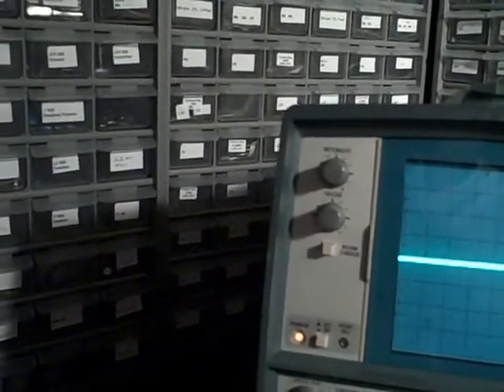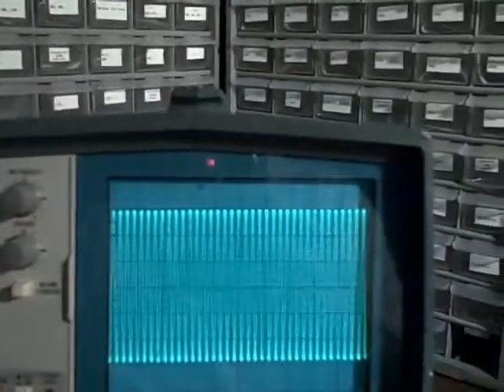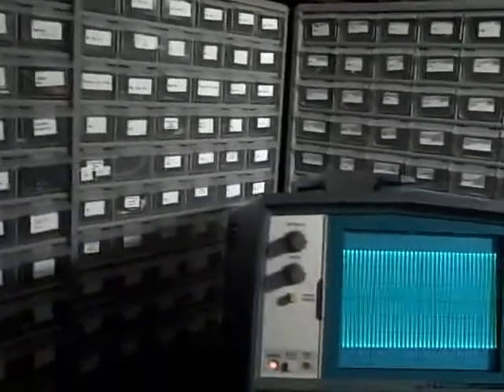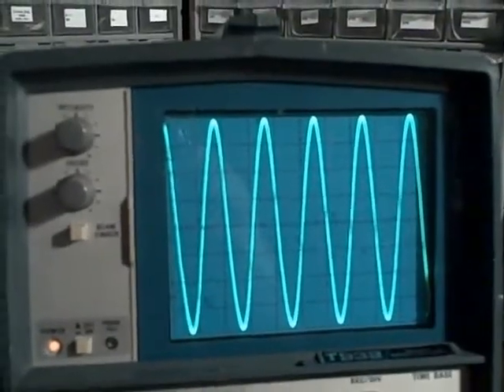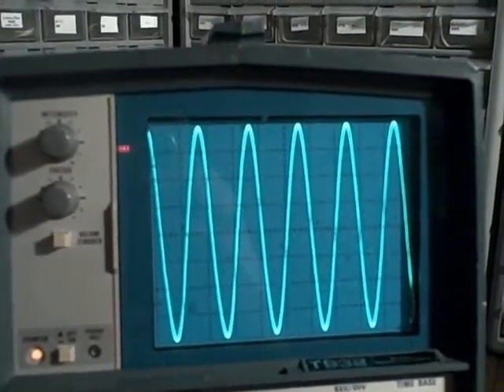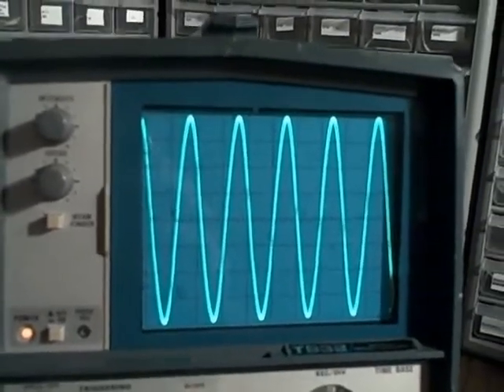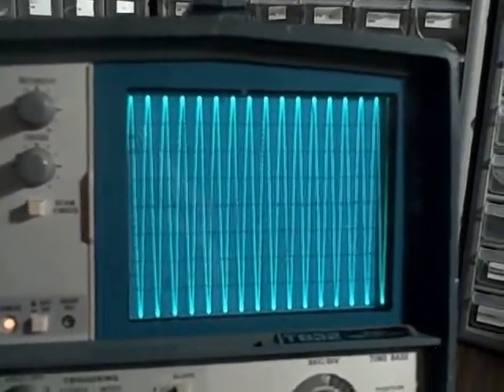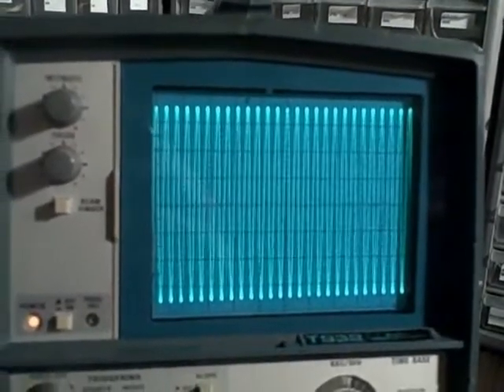Let's check channel 2. Alright, there's the 5 megahertz on channel 2, and we are traversing the entire 8 volts peak. Here's 15 megahertz, 25, 35. And once again, we're up about 3 divisions and down 3 divisions, so we're a little bit better than 35 megahertz bandwidth on both channels. So we pass.